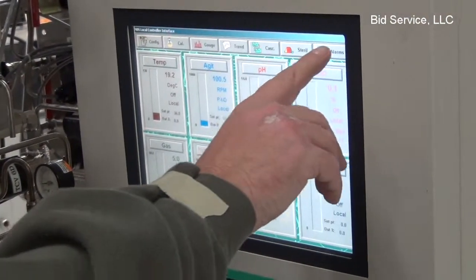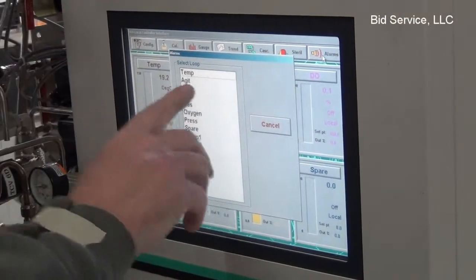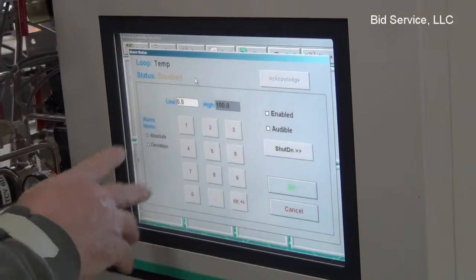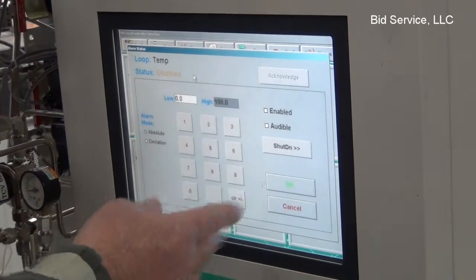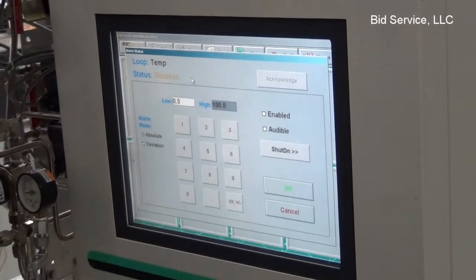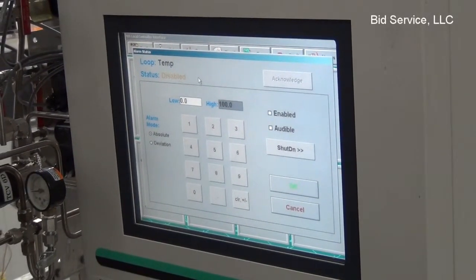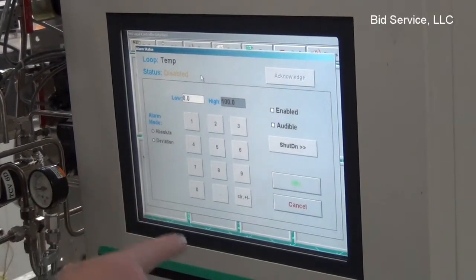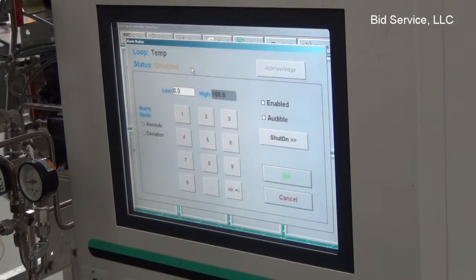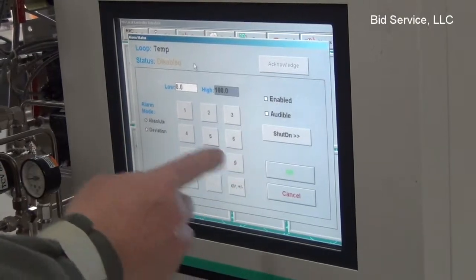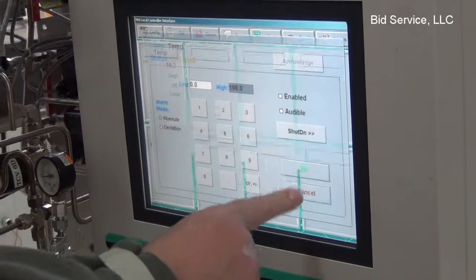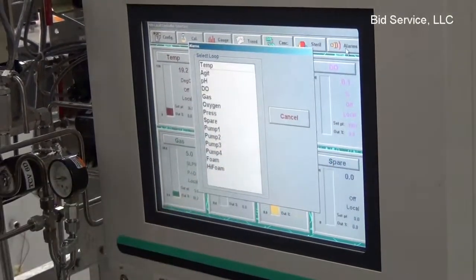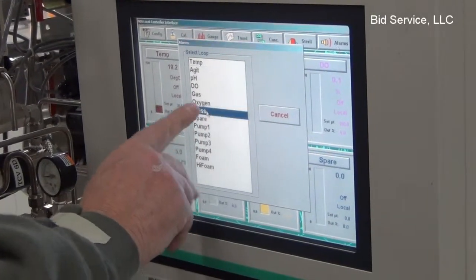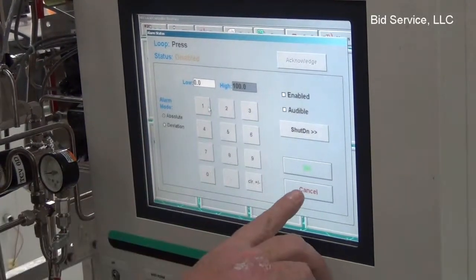Okay, and lastly over here is your alarms. Here you can go into a particular thing like temperature, have it low and a high, have it enabled, have it audible. You want it to shut down the instrument, etc. You want it absolute or just a deviation. So again, you can do that. Most of these have been disabled, but you can go into any one of these loops and do the same thing.